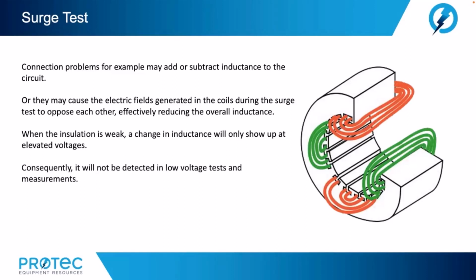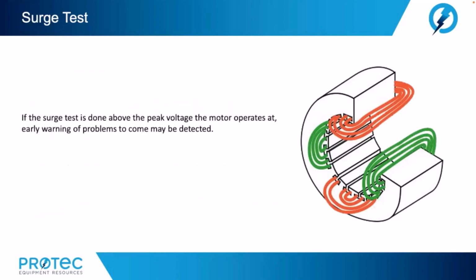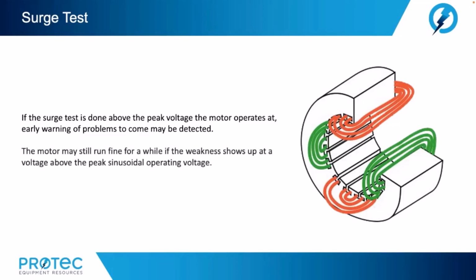Consequently, it will not be detected in low voltage tests and measurements. The surge test reduces false negative results, which is why the surge test is a very valuable test. If the surge test is done above the peak voltage the motor operates at, early warning of problems to come can be detected. The motor may still run fine for a while if the weakness shows up at a voltage above the peak sinusoidal operating voltage.